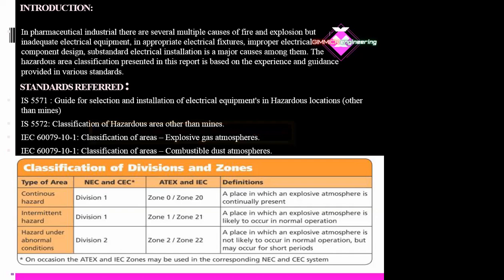This study is based on some standards: IS 5571, which describes the selection of electrical equipment to be installed, and IS 5572 for hazardous areas other than mines. We are speaking on chemical and API industries. The explosion of gas atmosphere is detailed in IS IEC 60079, clause 10.